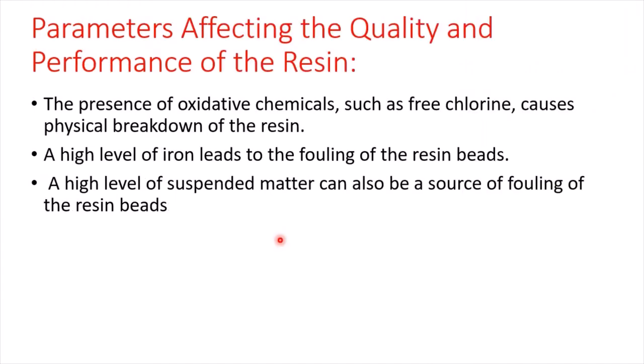There are some parameters that can affect the quality and performance of the resin. First, the presence of oxidative chemicals like free chlorine can cause the physical breakdown of the resin. If our water contains chlorine, we have to pre-treat it using a carbon filter, which can remove the chlorine. Also, a high level of iron can lead to fouling of the resin beads, and in this case we have to pre-treat the water using an adequate method.